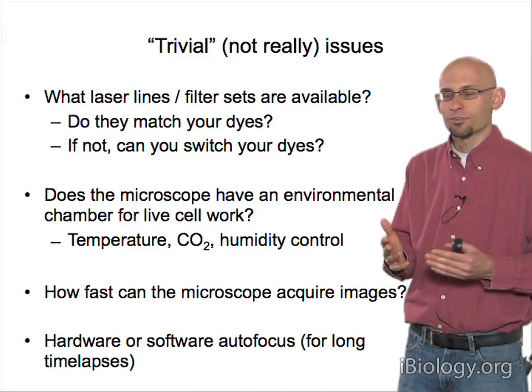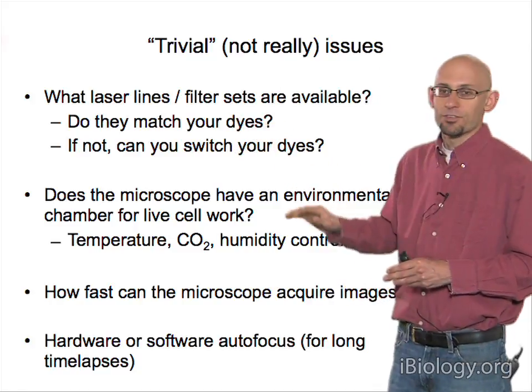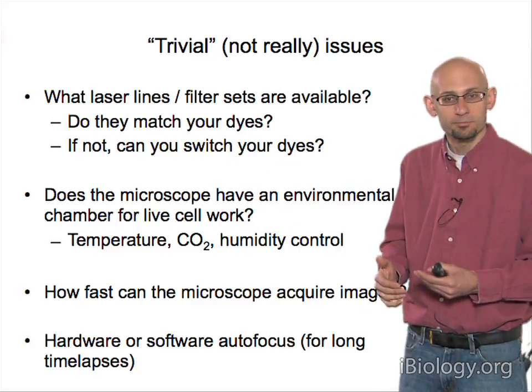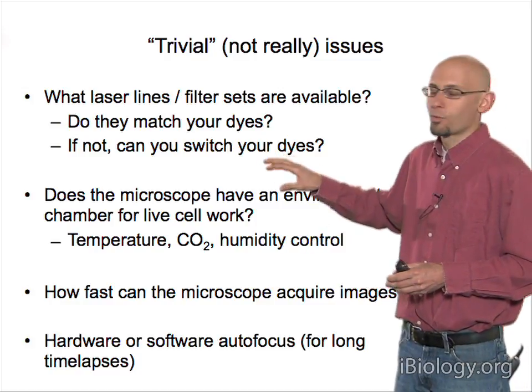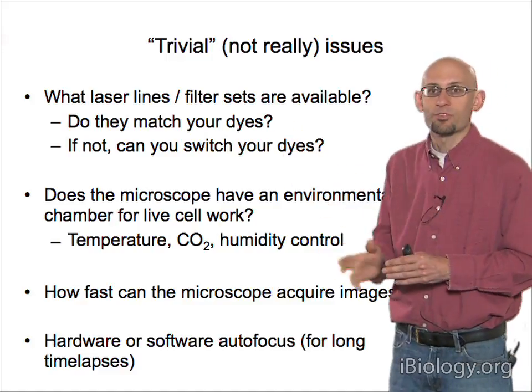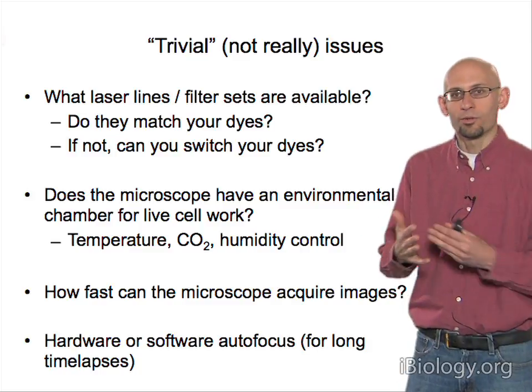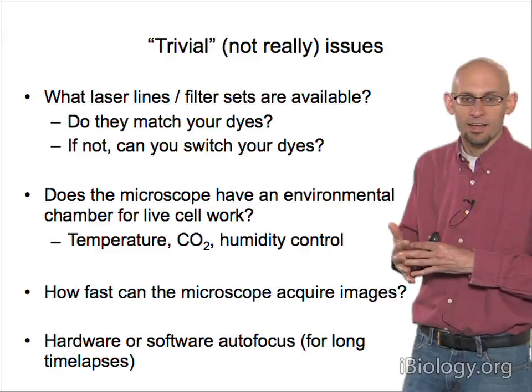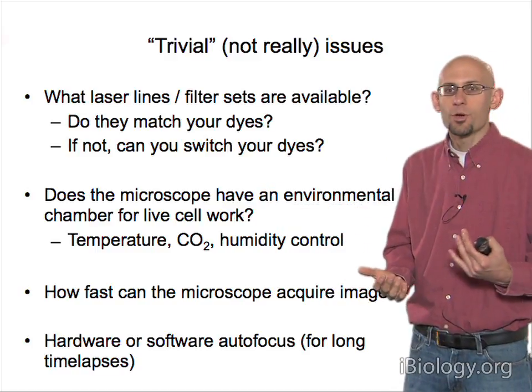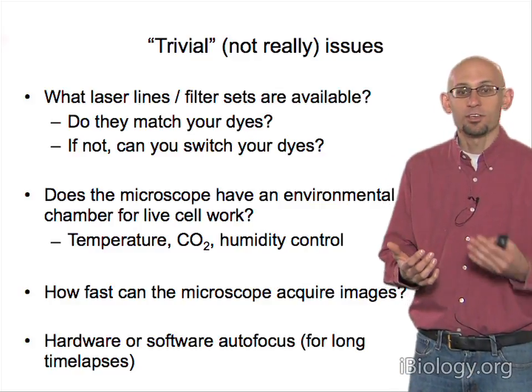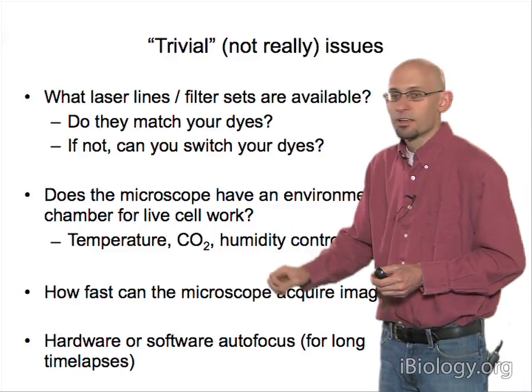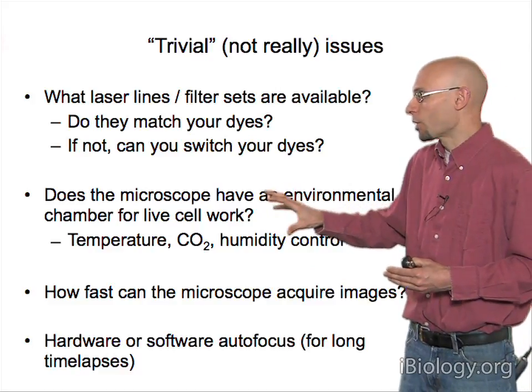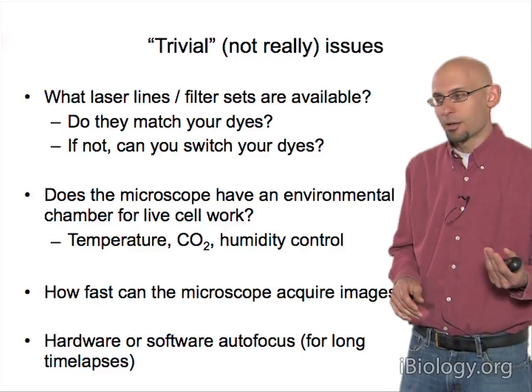Particularly if you don't have access to a wide range of microscopes, a critical question is what laser lines or filter sets are available, whether they match your dyes, and if not, can you switch dyes or add lasers or filter sets. On a confocal, adding laser lines can cost tens of thousands of dollars, so it's worth designing your experiment to work with the scopes you have. For live cell work, does your microscope have temperature, CO2, and humidity control? Mammalian cells need all three; other organisms may need just temperature and humidity.